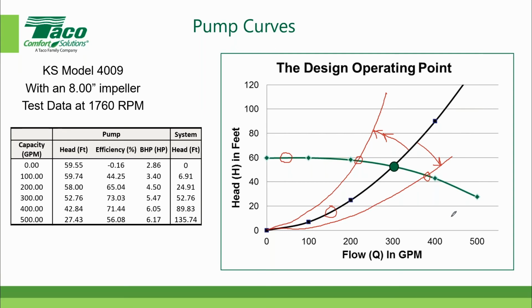Now, at one time in history, we didn't have variable speed pumping. We just simply allowed the two-way valves to open and close, and then the system curve would, we used to say, would ride the pump curve up and down. And that worked reasonably well as long as you didn't have major pressure differentials in the system, and it didn't save a lot of energy. So we're going to talk a little bit now about self-sensing pumps. And how do we generate the data for self-sensing pumps?